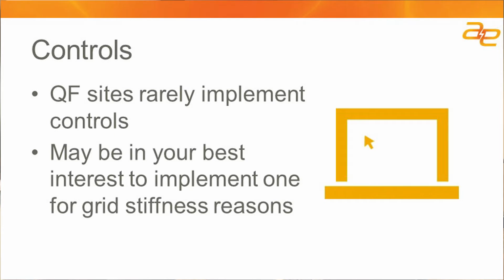So if you look at what has historically been done at these QF sites, I very rarely see a site that has a control system in it unless it's a requirement of the interconnection agreement. And that doesn't happen very often. So typically you've got a site with a recloser that's controlled by the utility most of the time. Then you've got medium voltage coming into one or multiple transformers on the site, and then inverters that are just designed to run at whatever their Pmax, or their maximum power output, is configured for, so that you can achieve the output of the plant as designed.